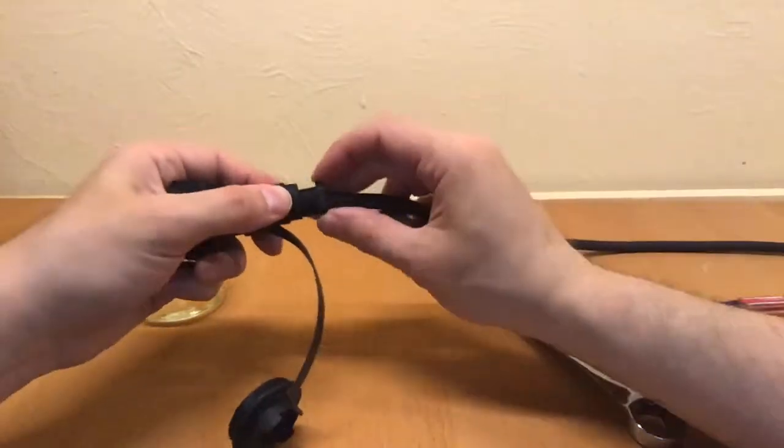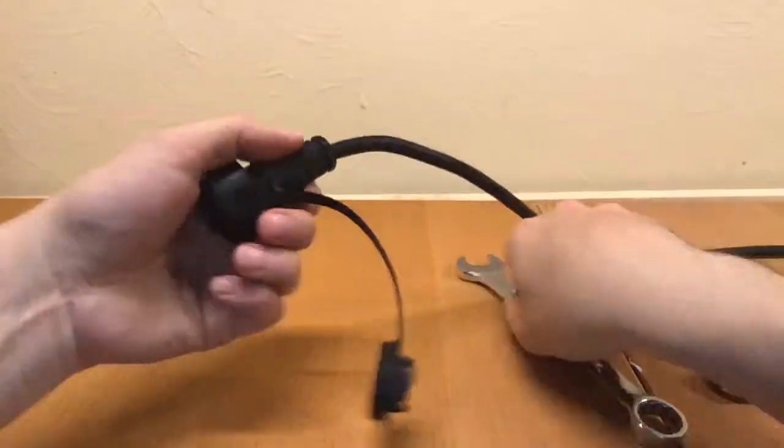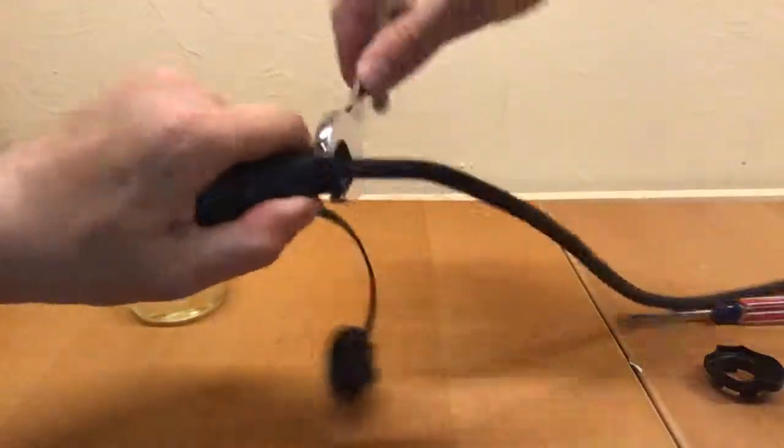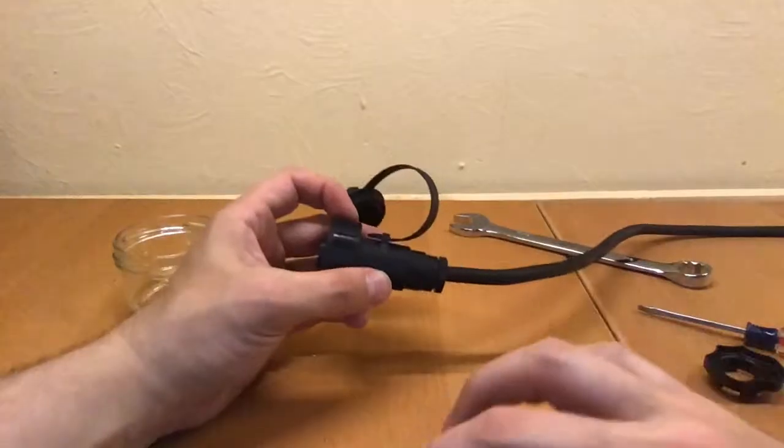And then we're going to take the screwing bolt, put it in place. Once it's there and you cannot screw it by hand anymore you're going to want to do about one and a half more turns with a wrench. And you have a fully assembled connector.